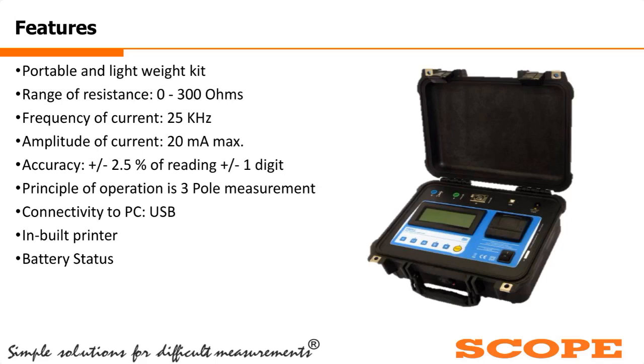For that, in India, we are supplying it through our partnership with Tentec. Tentec is a Megabras company's authorized dealer, which works in the USA. For the tower footing resistance meter, we have a resistance range of 300 ohms. It works on a frequency of 25 kilohertz, and the maximum amplitude of the current is 20 milliampere. Our kit can give you results with an accuracy of 2.5% of reading plus or minus one digit. It works on the principle of three pole measurement.